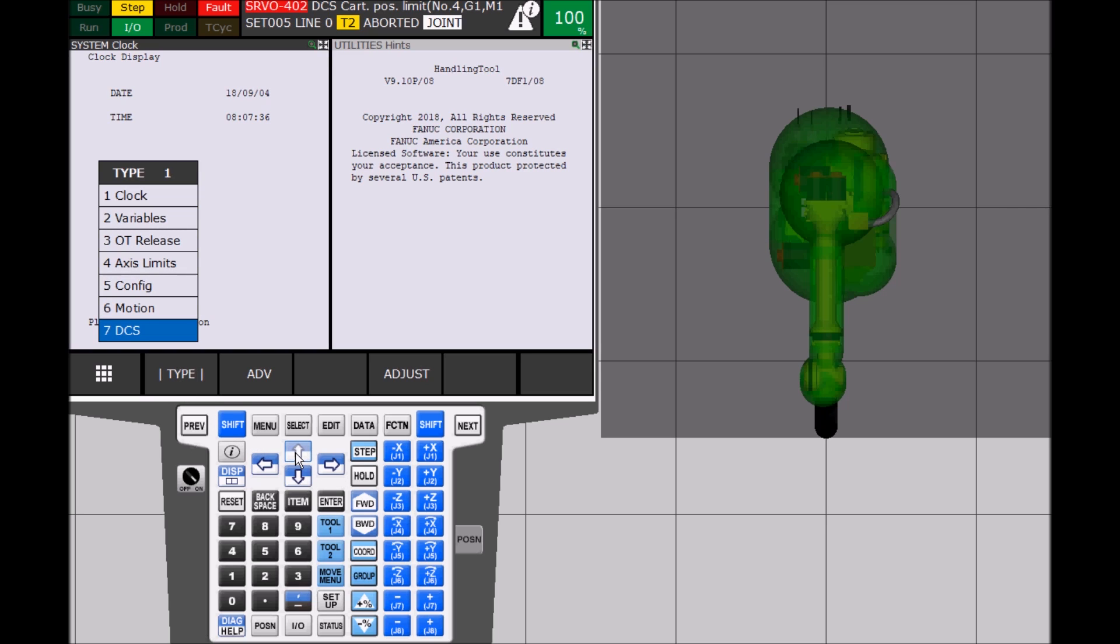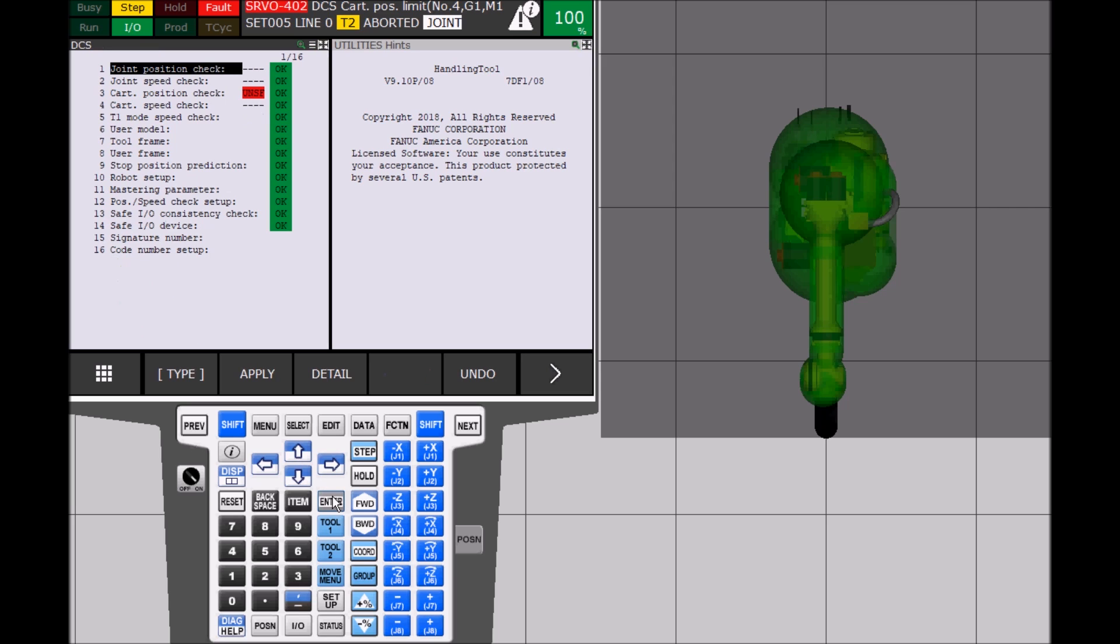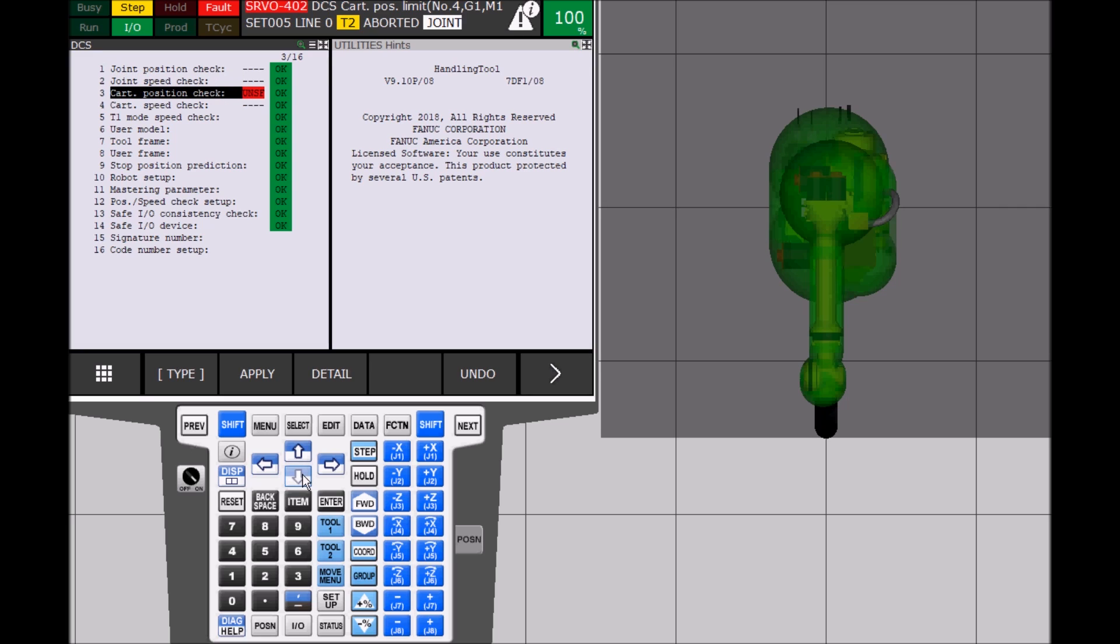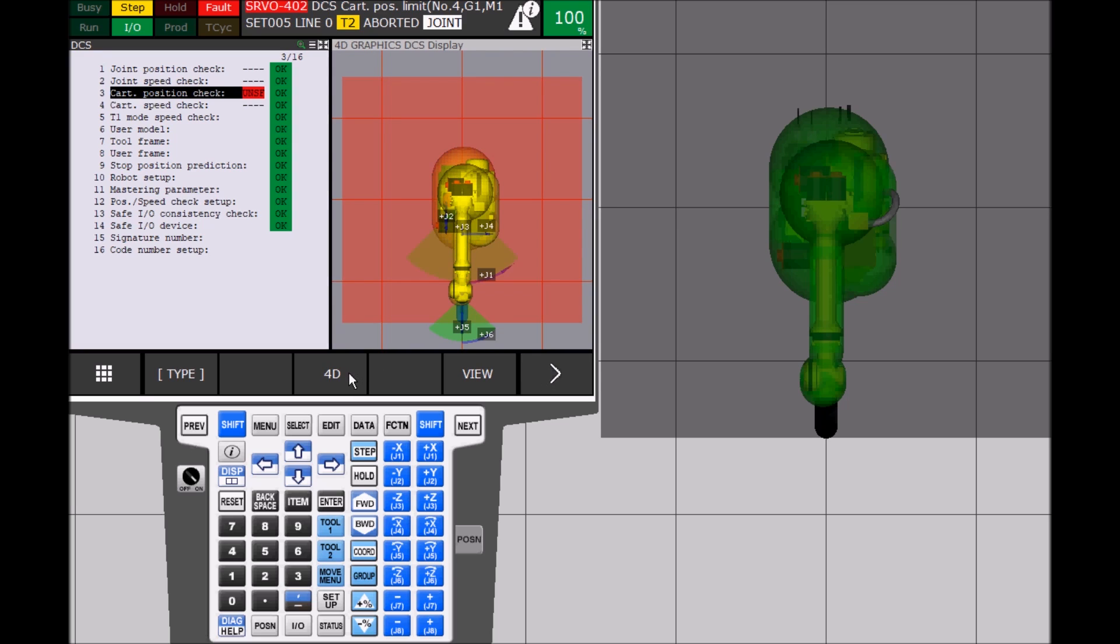The DCS screen shows a list of DCS parameters and the Cartesian position check parameter is marked as unsafe. Right scroll the lower bar menu until you see 4D. A model of the robot pops up on the right side of the screen. You can see that the zone is red, meaning the robot cannot move.